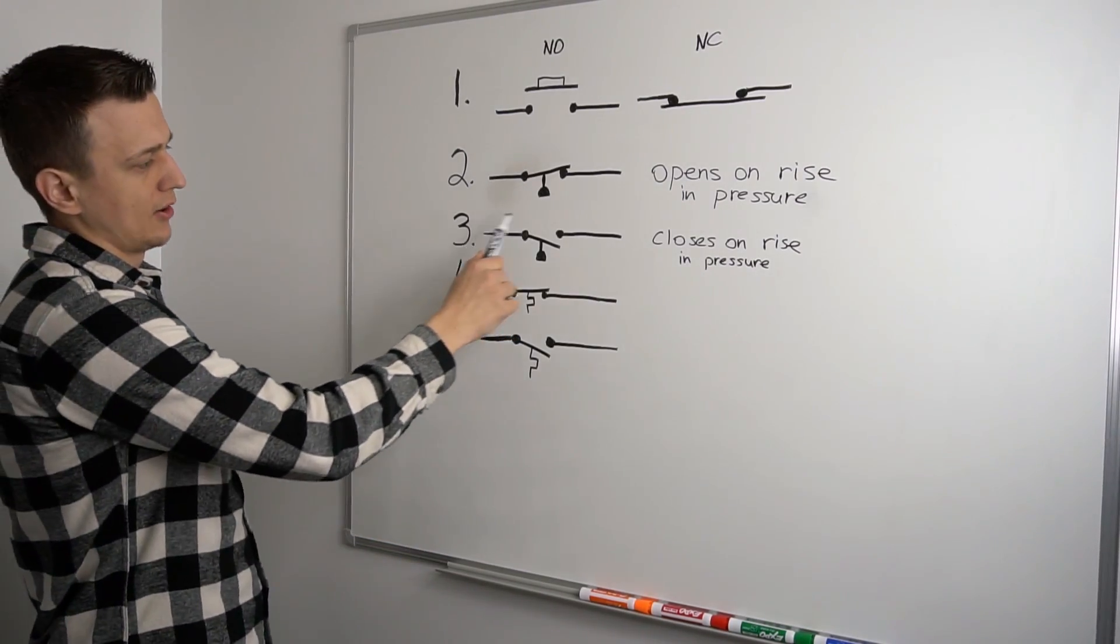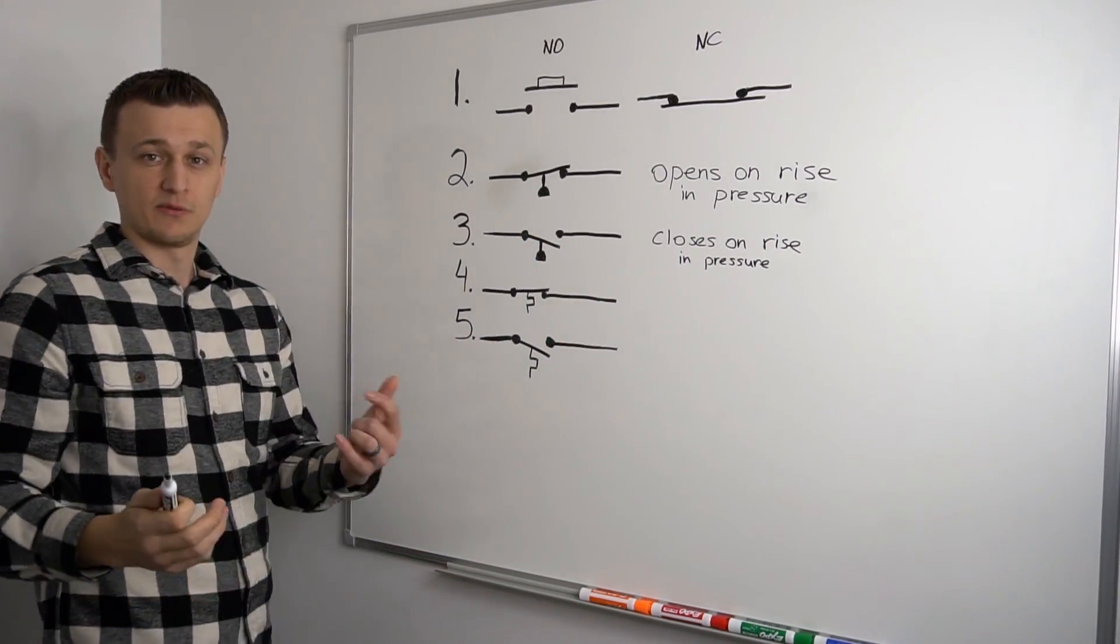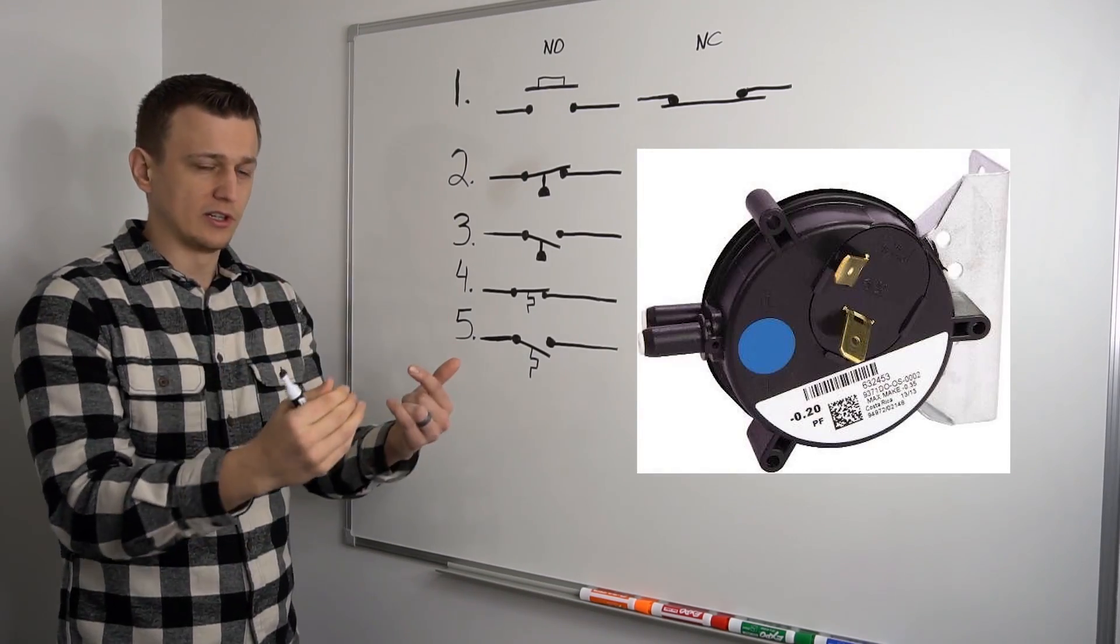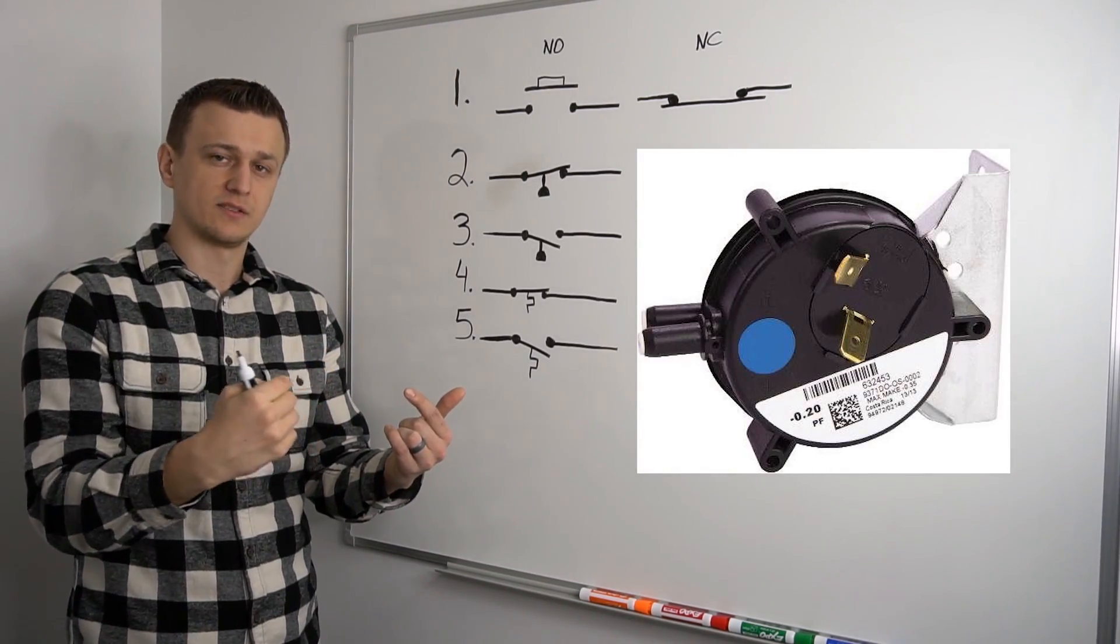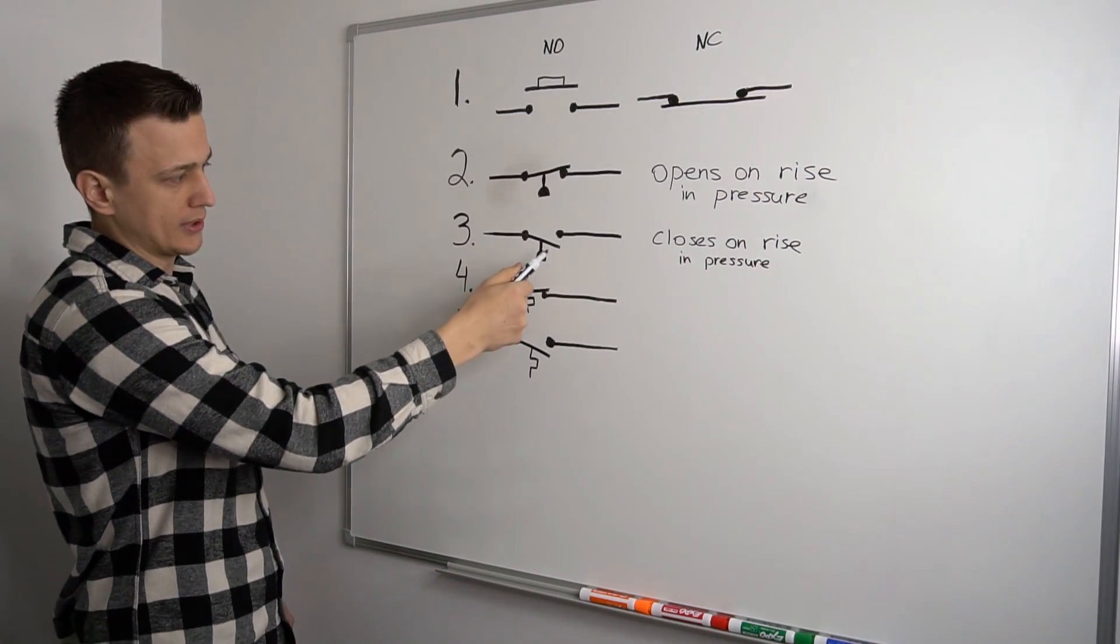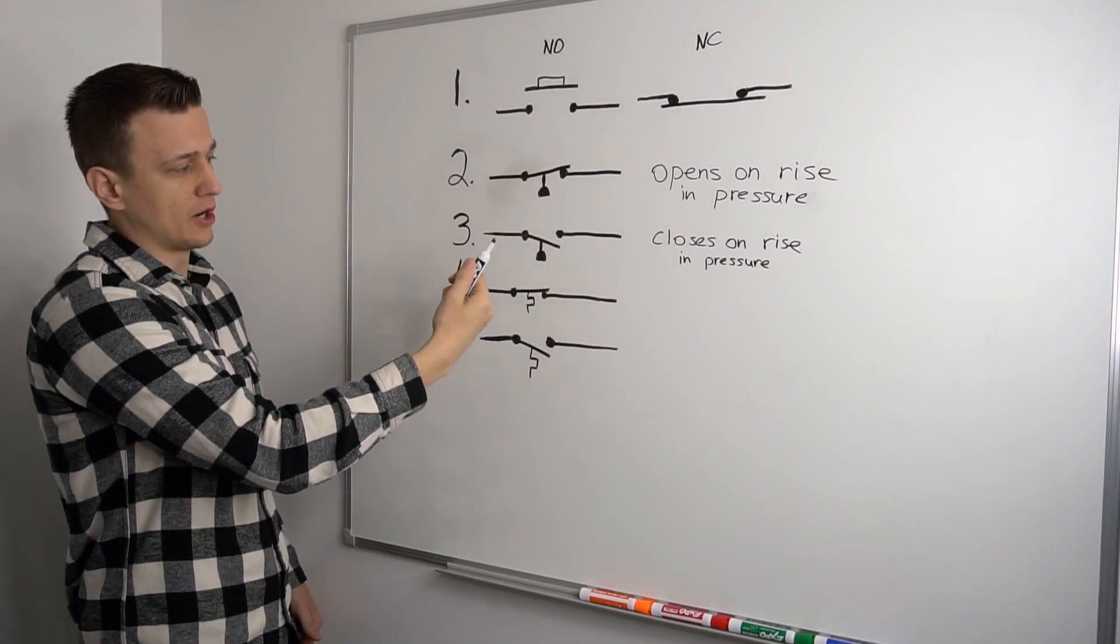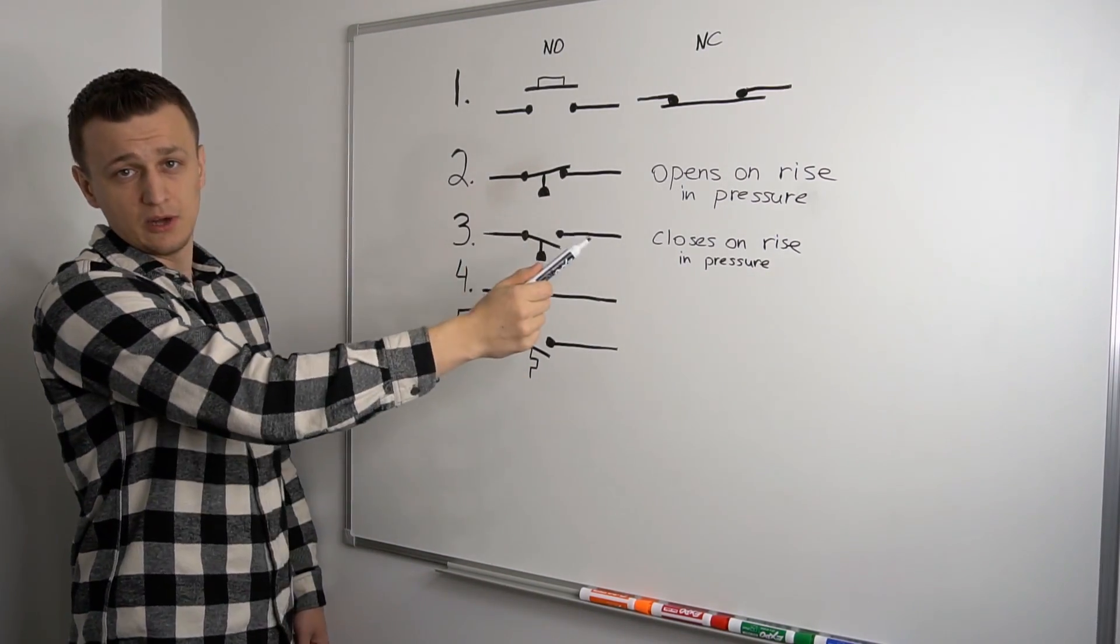So an example of this, a normally open pressure switch would be in the furnace. So the inducer motor turns on. And in order to prove that there's a draft that it's venting properly, this normally open pressure switch, the air pressure will close it and allow the power to go through.